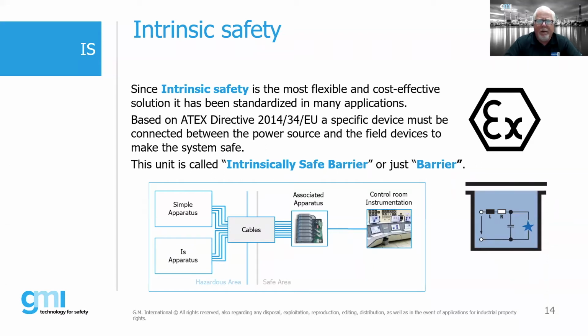So basically, there's a term that we use. If you see the slide below, you have what is called simple apparatus and intrinsically safe apparatus. We have cables. The associated apparatus is what we typically call our intrinsically safe barriers or barriers. So when you hear the term associated apparatus, that's another term for an intrinsically safe barrier, or in some cases, people will call them isolators. And then finally, you have your control room, which is providing the signal out to the field.